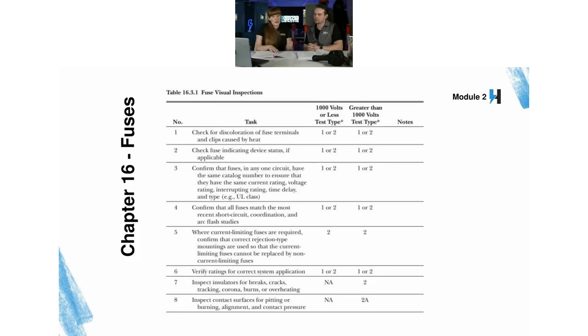Looking at table 16.3.1, almost every chapter with equipment-specific inspections, cleaning, and servicing has tables like this. So check for discoloration—these tasks are specific to chapter 16, fuses. Chapters 11 through 16 have specific equipment and specific tasks you need to follow for each piece of equipment. A lot of them might be similar, but there are specific steps that could be very different than what this fuses table says.